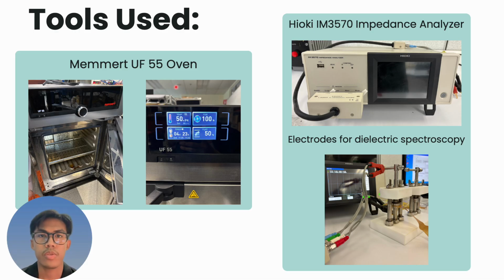The first tool used is a fan oven, which serves as an alternative to a vacuum oven for drying and impregnating kraft paper with oil. Although it lacks vacuum capability, it enables controlled thermal treatment. So I use the fan oven for aging, where I set the parameters, for example temperature to 80 Celsius and the aging days to 5 days. Then the oven stops automatically after the preset time.